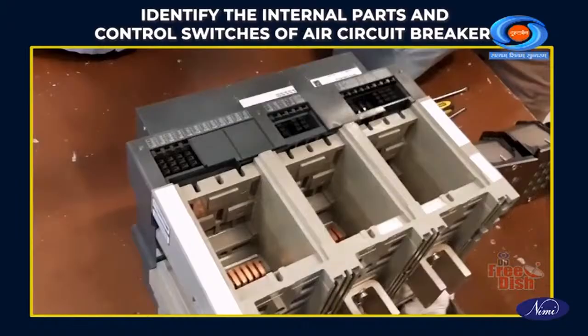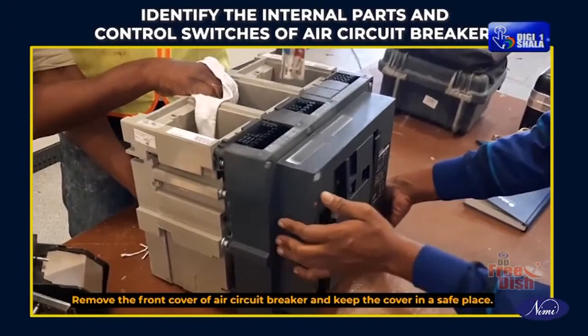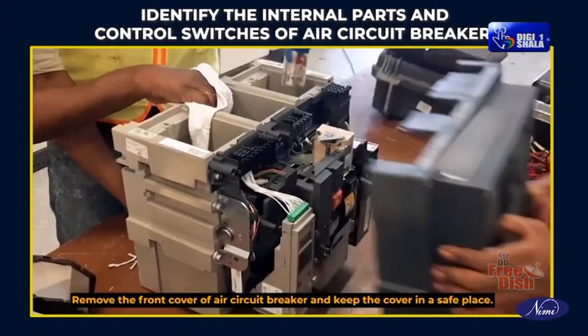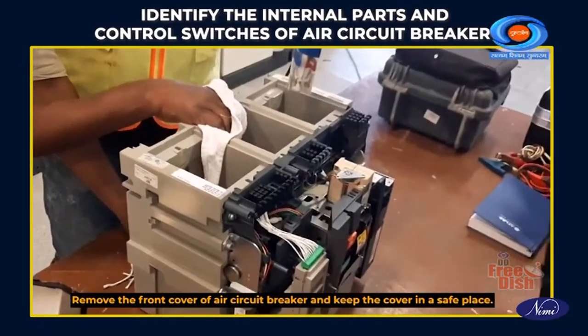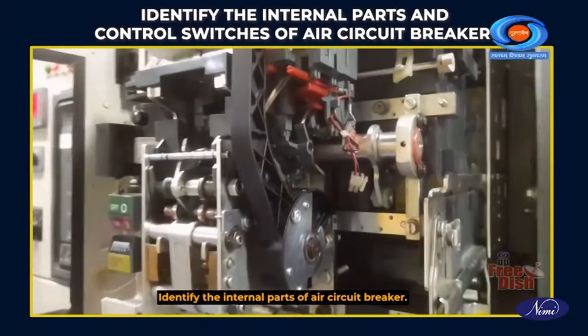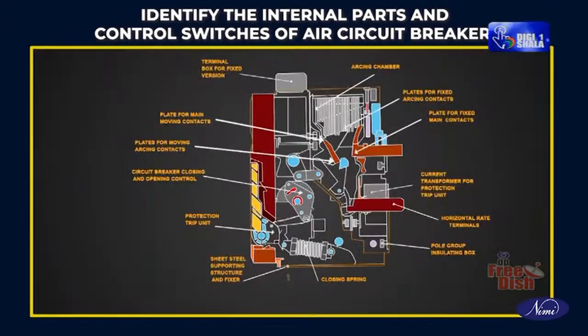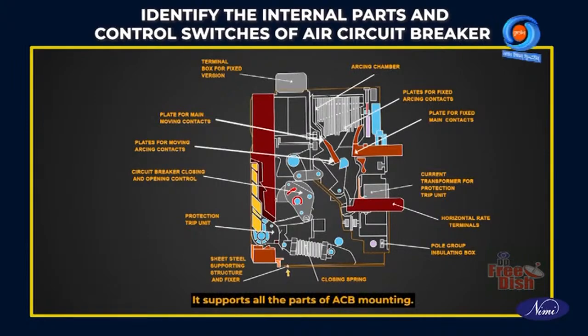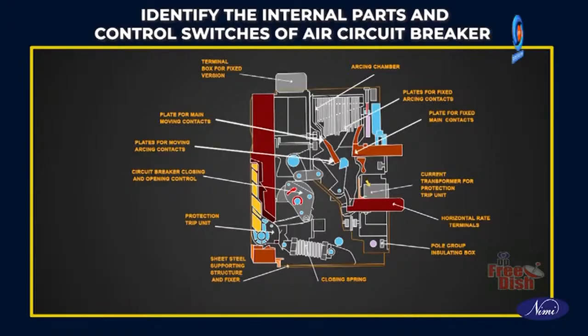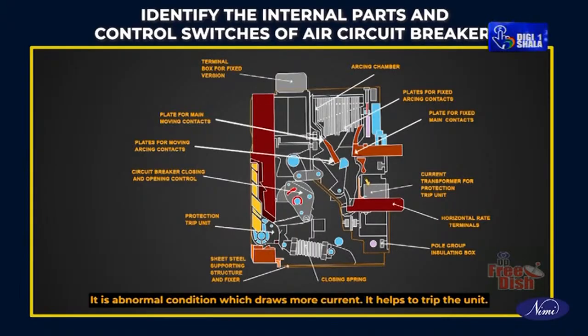Identify the internal parts and control switches of the air circuit breaker. Remove the front cover of the air circuit breaker and keep the cover in a safe place. Identify the internal parts. Sheet steel supporting structure and fixture: it supports all the parts of the ACB mounting. Current transformer for protection trip unit: in an abnormal condition which draws more current, it helps to trip the unit.